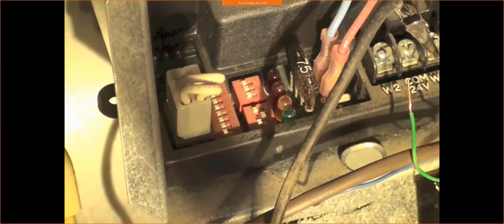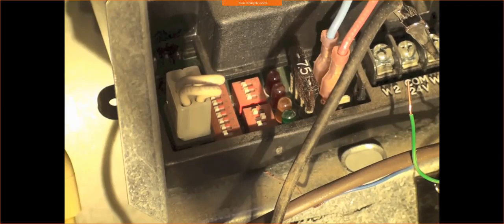Okay, this code we're reading here is an ignition failure code. It means the burner did not light for whatever reason. Could be the gas off, could be flame rod not sensing, could be hot surface igniter not working. But for whatever reason, it did not sense flame. That's a 34 code, and it's going to try 3 times, and then we'll see what code it goes to when it goes in hard lockout. Right now it's in soft lockout, and it's retrying to see if it can ignite the furnace.